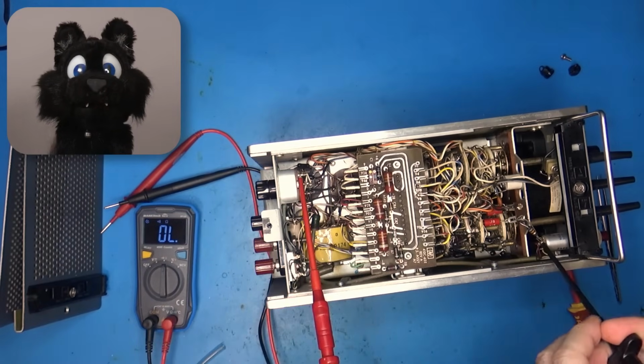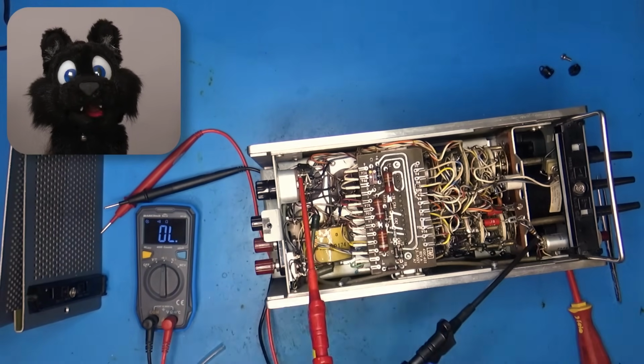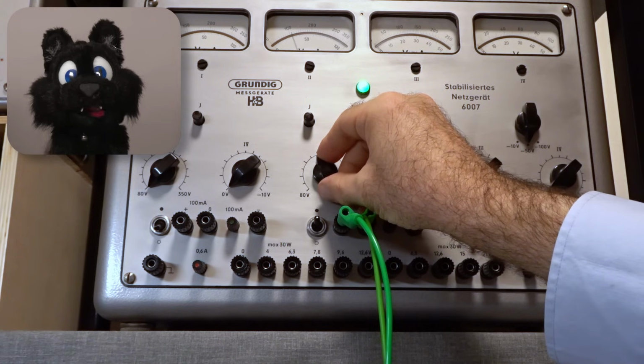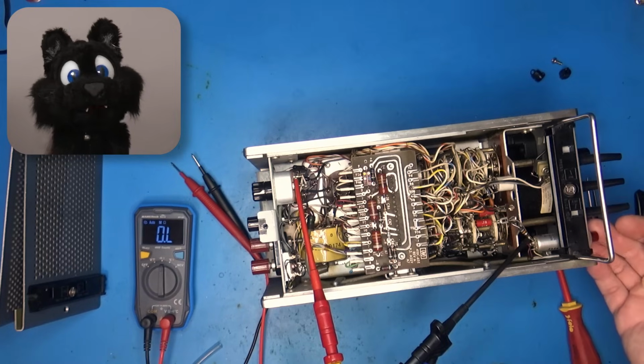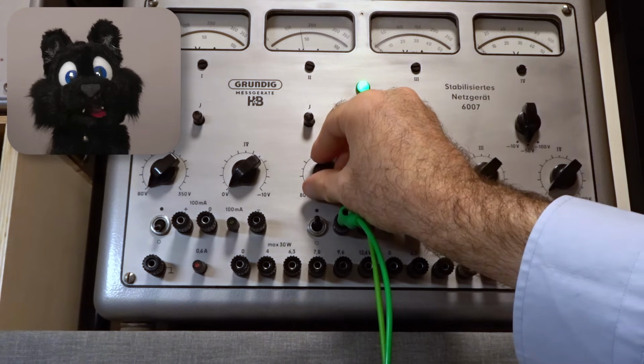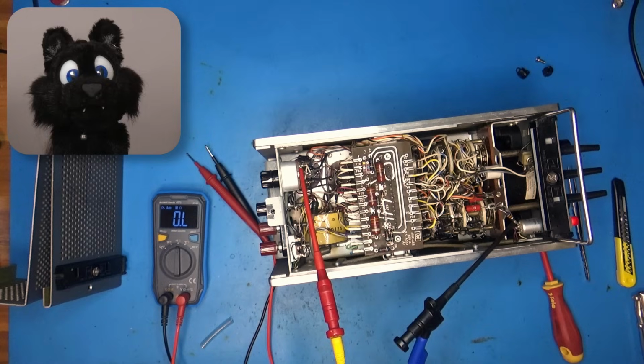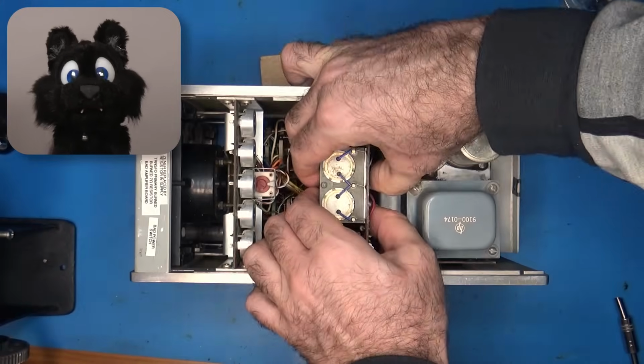Checking the neon indicator inside the switch next. It is wired into the 150 volt path of the primary, so it should light up at about 100 volt, give or take. But no, after cranking up the voltage a bit, it does come on at about 130 volt, which is way too high. The bulb must be on its way out.